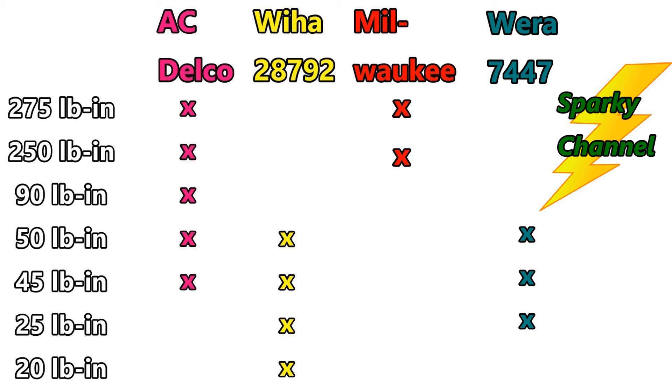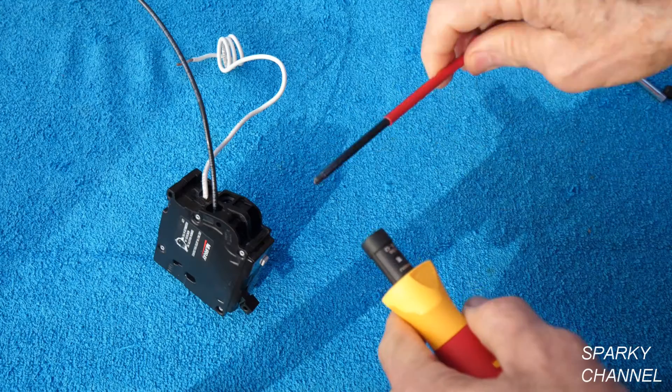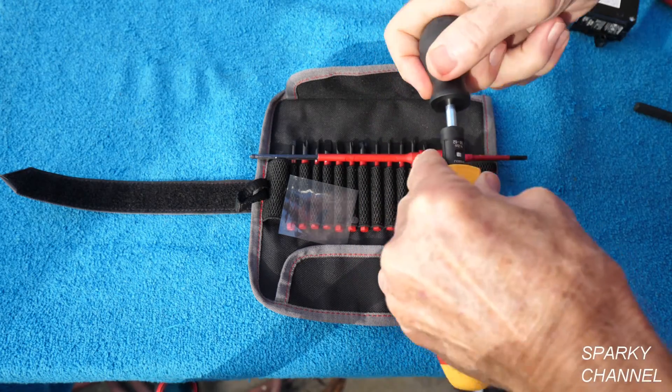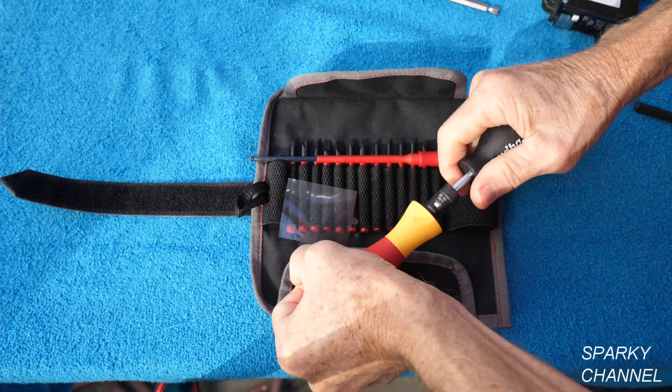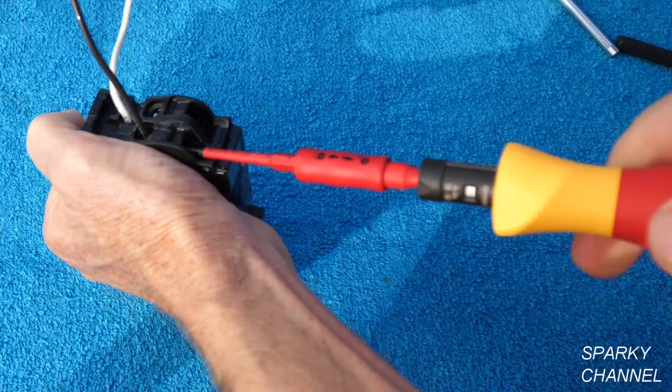The best combination for torquing in this panel is the AC Delco and the Wiha. The Wiha is definitely the best for changing out breakers in a live panel because it's 1000-volt insulated. So my picks for best torque devices for electricians are the AC Delco 3/8-inch torque wrench and the Wiha 1000-volt insulated torque screwdriver. It has 13 fully insulated bits, a fully insulated torque holder, and a tool with which you change the torque setting. It also has a nice click when you reach the torque setting.